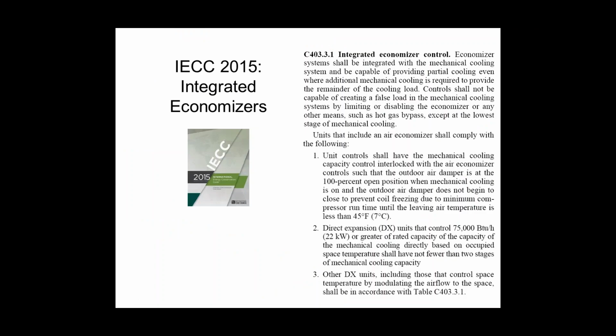Next thing on economizers, like I said, is you have to have an integrated economizer. Anytime you have an economizer, it's required to be integrated. So why they made a separate section for it and didn't just list this language in the regular economizer section, I don't know. But if you have an economizer, it's got to be integrated, which means you have to have the ability to run the compressor in conjunction with the economizer damper for free cooling.